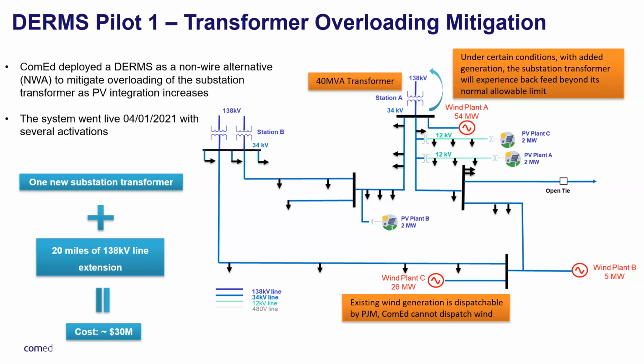We saw several activations of PV shedding events in the past, especially when there are topology changes. We have two substations connecting to the PV and wind plants, and usually the PV and wind feed back into those transformers based on the distribution factor. If the connection with one substation is cut off, the power flow changes significantly, increasing the distribution factor for those PVs into the transformer of interest, and that's when the curtailing event happens.